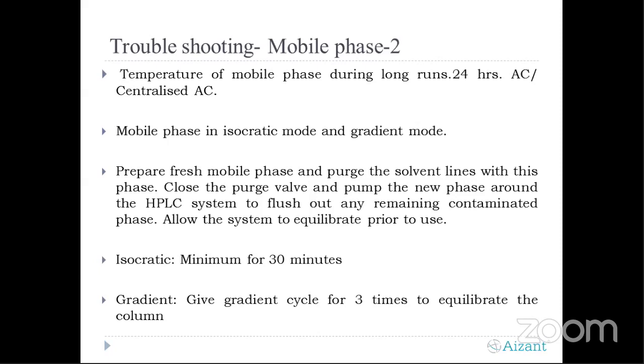And gradient mode depends on the pumps, which is not in our hand, because there are two compositions, A and B, or C and D, and it's up to the instrument. If it's not working properly, we'll again have a lot of retention challenges. Always use fresh mobile phases, and we have to equilibrate the HPLC system, either in isocratic mode or in gradient mode.